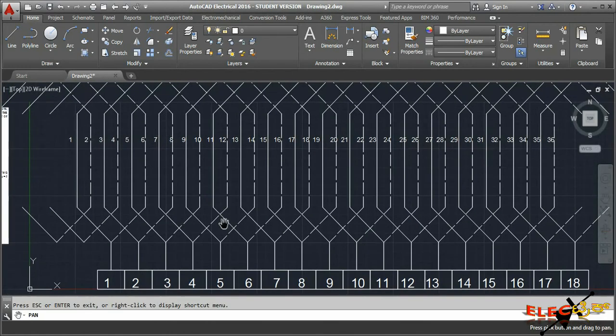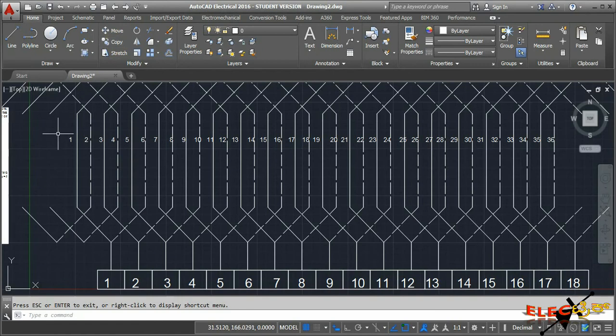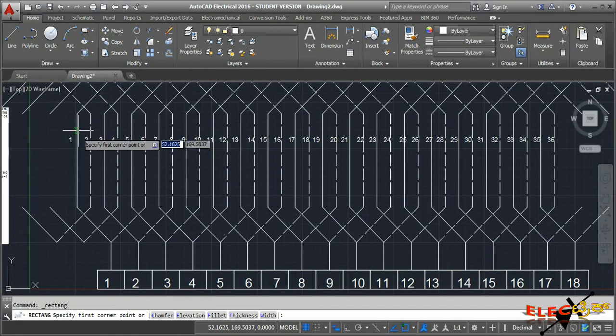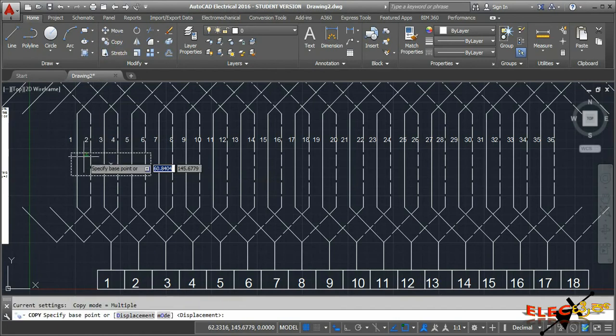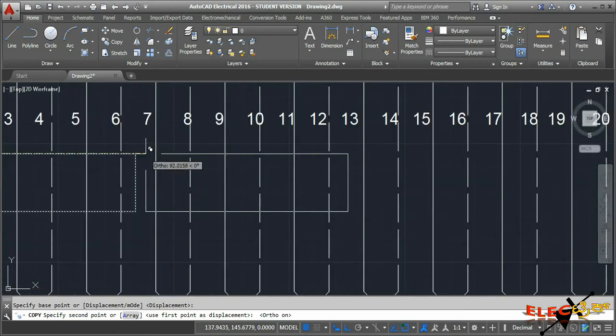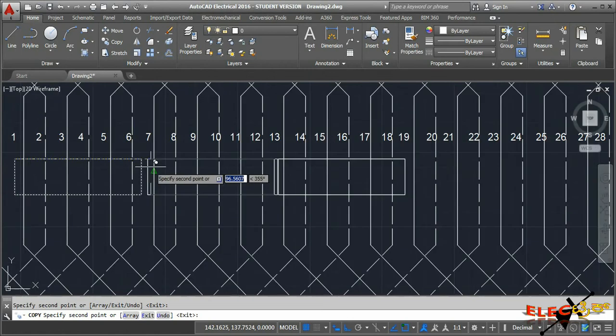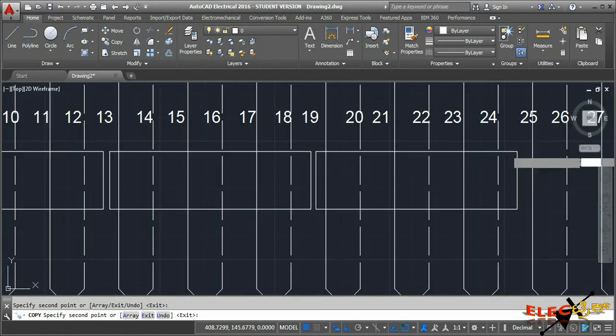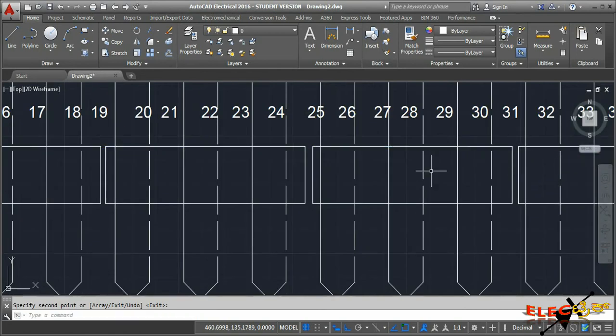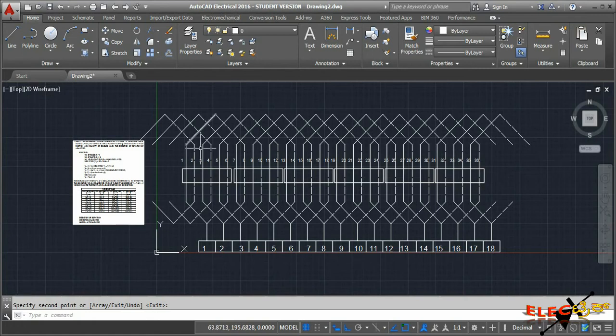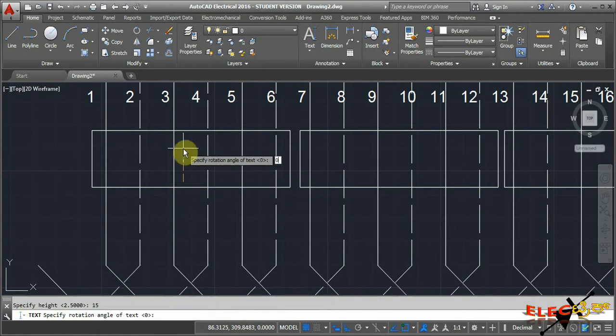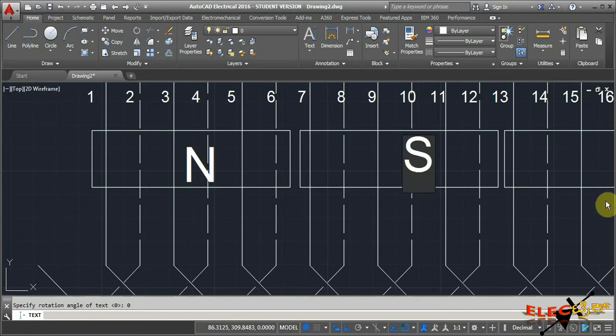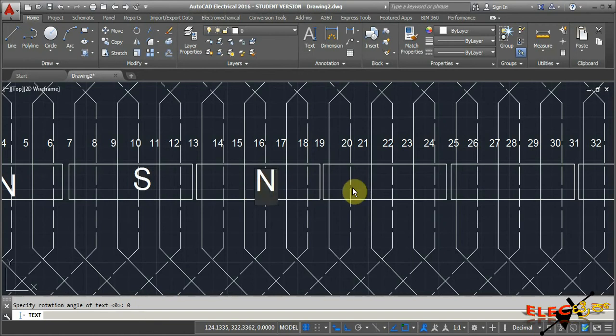After numbering the 18 commutator segments, we show the poles. There are six poles and each pole covers six conductors since pole pitch is six. Draw a rectangle covering six conductors and copy it along the winding to place all six poles. Name them alternating North and South.